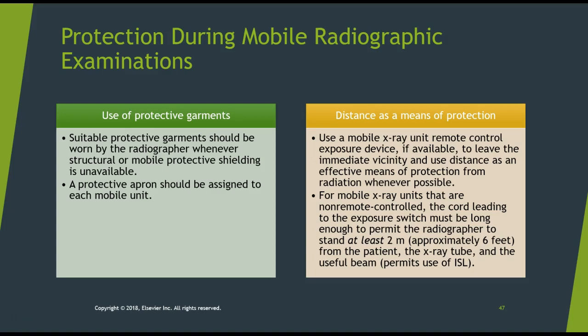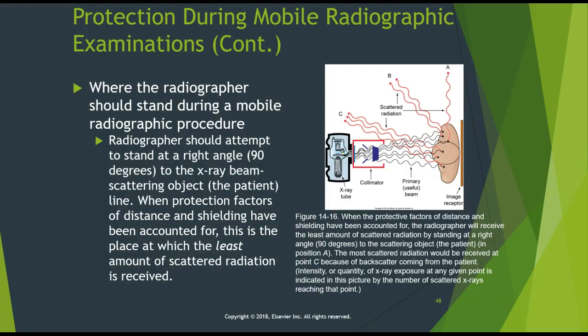If you do not have a remote control available, the cord leading from the switch must allow you to be at least 2 meters from the patient, the X-ray tube, and the useful beam. So stand back as far as possible before you hit that exposure button. Now this right here, this is mobile radiography we're talking about. This is where you should stand during mobile radiology procedures.